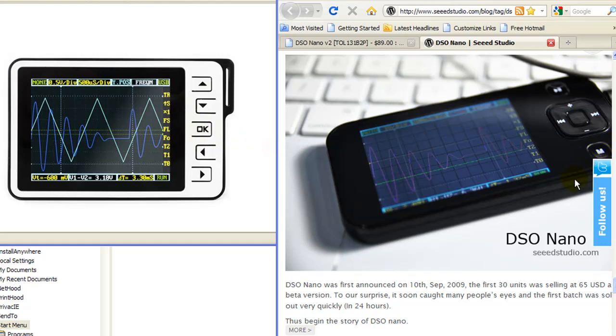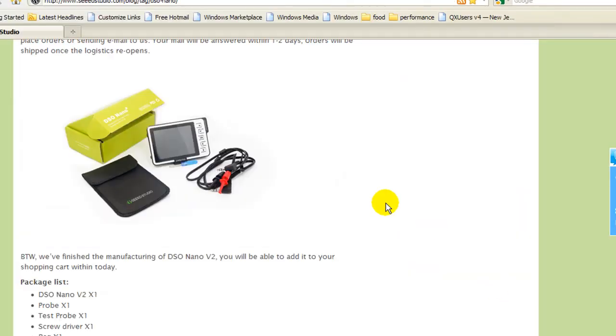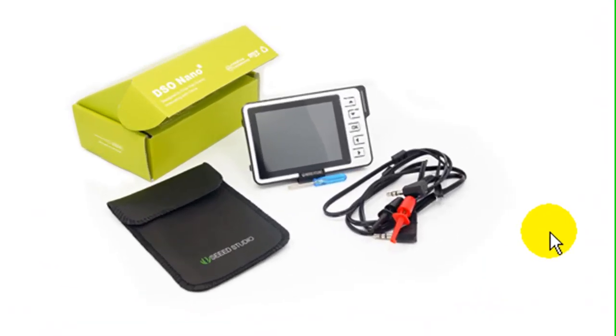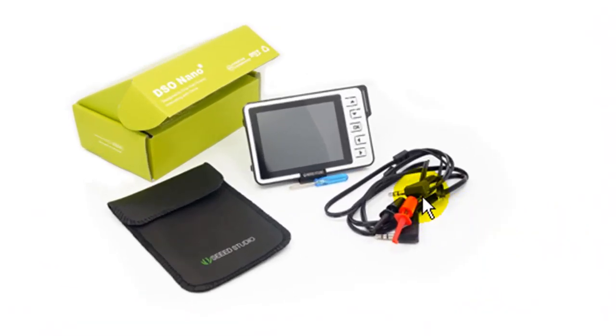And the other difference between the two units has to do with connecting the probe compensation signal. So let's take a look at that. When we connect the compensator signal with the version 2 hardware, you will need two probes. Two probes come with the unit. One probe will plug into the probe compensation signal, and the other probe will plug into the channel 1 input to the oscilloscope. So let's take a look at these two probe locations.